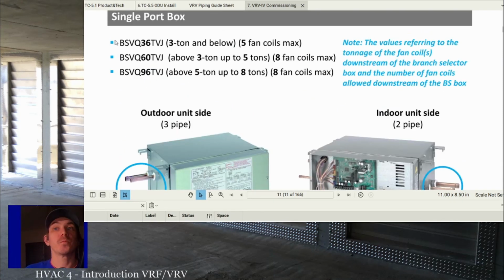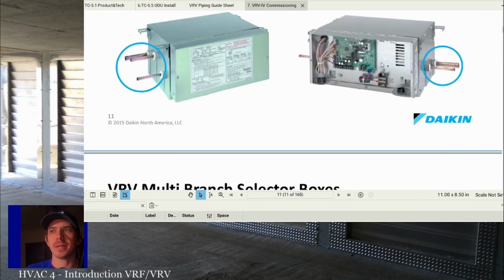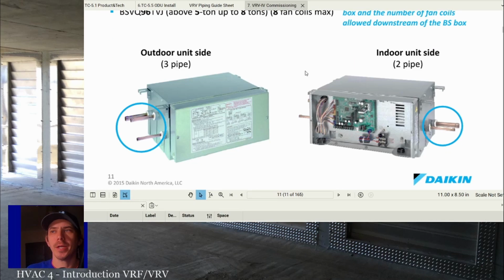And from the nomenclature on these, and this is again pretty standard across the board, you can tell 36 is 3 tons, 60 is 5 ton, 96 is 8 ton. So when you see the model number, you can tell how many tons that branch selector box can carry.